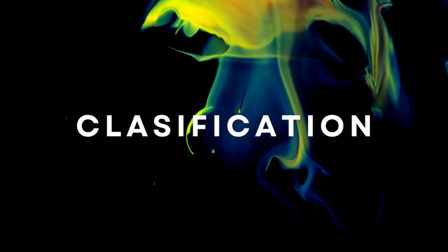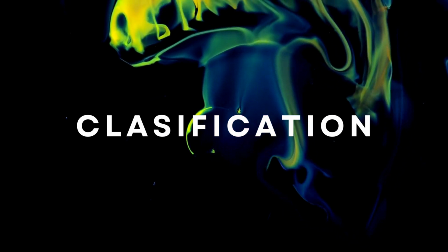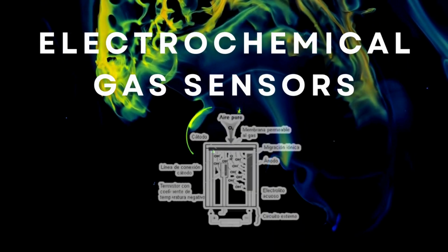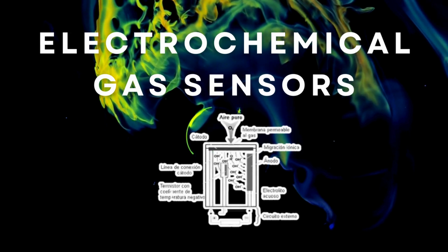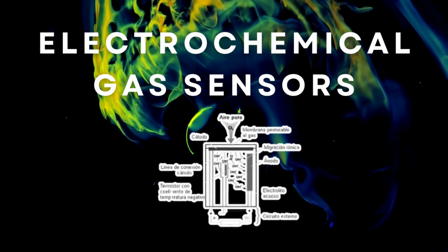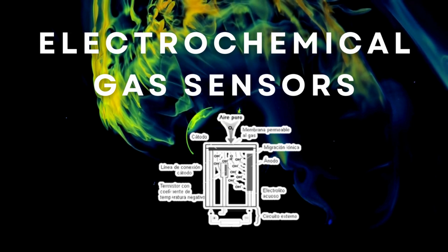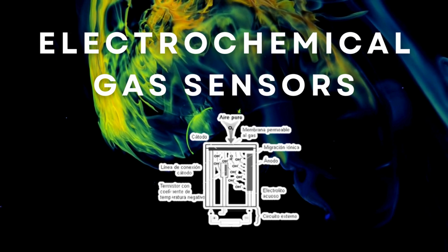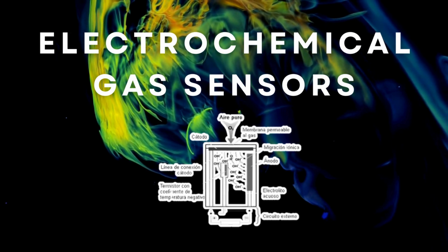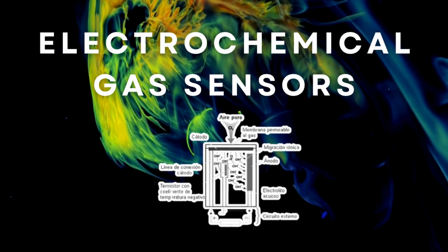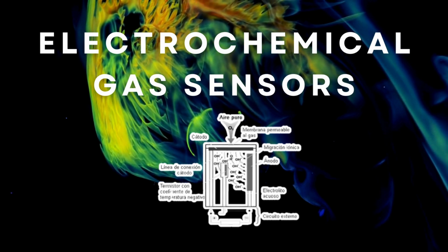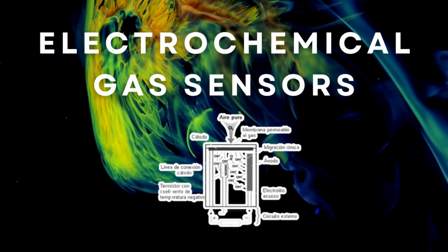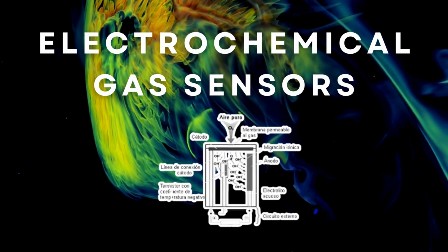Now let's talk about the classification of gas sensors and the physical principle behind them. Electrochemical sensors use chemical reactions at electrodes to detect gases. In an electrochemical sensor, an electrolyte solution is in contact with three electrodes: a working electrode, a reference electrode, and a counter electrode. When a specific gas comes in contact with the working electrode, an electrochemical reaction takes place that generates an electric current. The intensity of the current is directly related to the concentration of the gas in the environment.